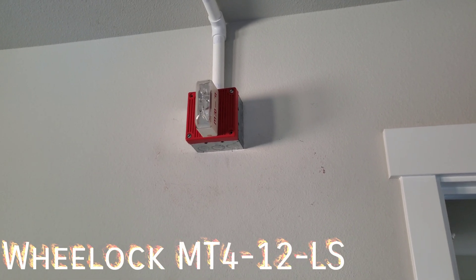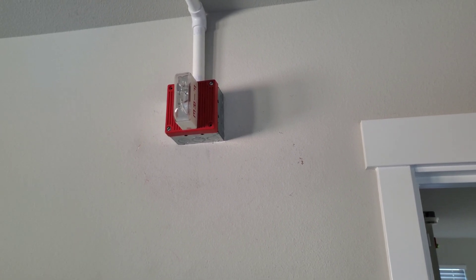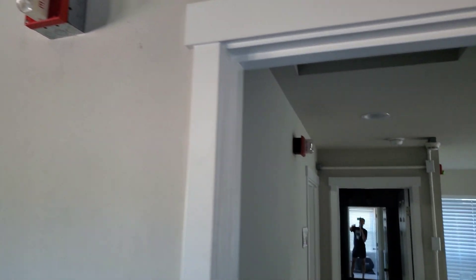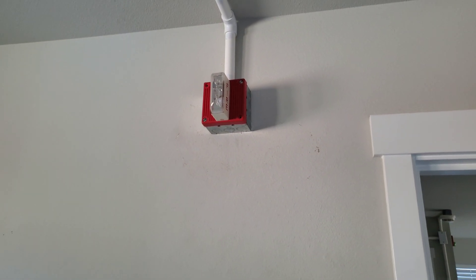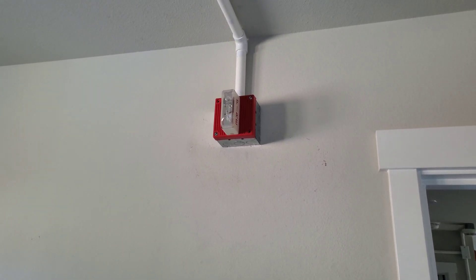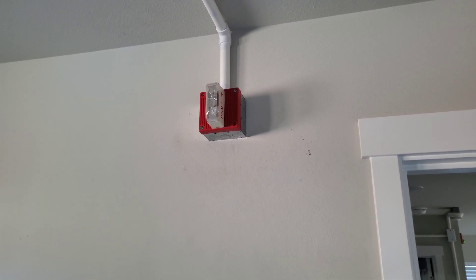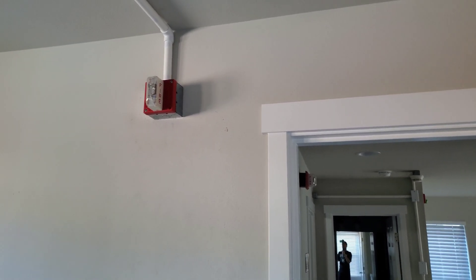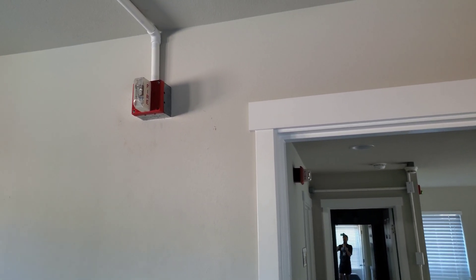Same carbon monoxide alarms. In the gym we have another NBG-10L, and the MT4-12LS Wheelock. It is 12 volt but set on the 24 volt setting, also set on siren. This is a 15 candela strobe — it's an LS, not an LSM — and it has a really fast strobe rate at four flashes per second. If you have photosensitive epilepsy, I suggest you don't watch the test portion.